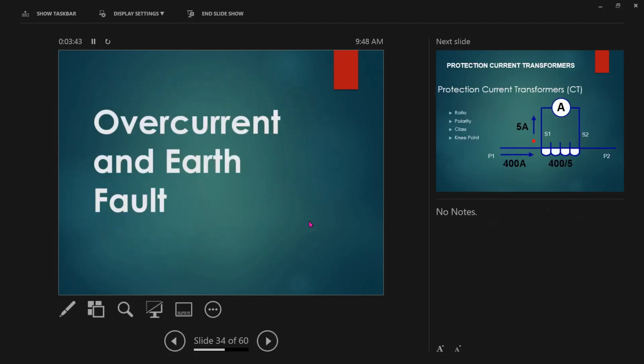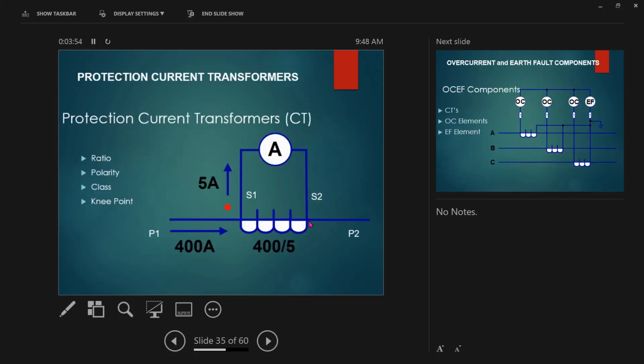Okay, so overcurrent and earth fault. I can probably try to explain this as much as I can in layman's terms. It's a bit technical, but I'm just giving you some kind of overview of how the current flows. The protection current transformer is a current transformer with ratio, polarity, and class, whether it is protection class or metering class, and the knee point, the one that we saw in the CT analyzer.